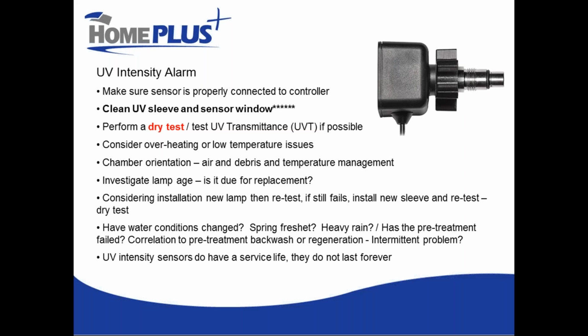So when the intensity sensor is mounted on a horizontal chamber and it's on the top of the chamber, it tends to be an area where air pockets or any air passing through the water lines tend to accumulate. Those little air bubbles will interfere with the readings of the sensor. And on the converse side of things, if the sensor is mounted such that it is on the bottom, it becomes a little bit more of an area where debris will settle.